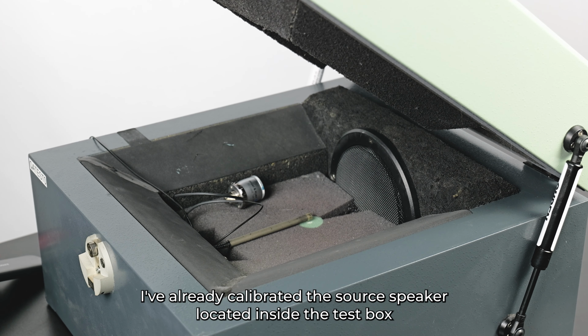I've already calibrated the source speaker located inside the test box using my SEM reference microphone pointed at the source speaker. The coupler is configured with a 1/2-inch microphone capsule, and we'll attach our hearing aid to the coupler's input. We have some tack here to get a good seal. Now, we'll put it in the test box so its microphone port is located at the same position I had the reference microphone. Let's close the box and we're ready to test.